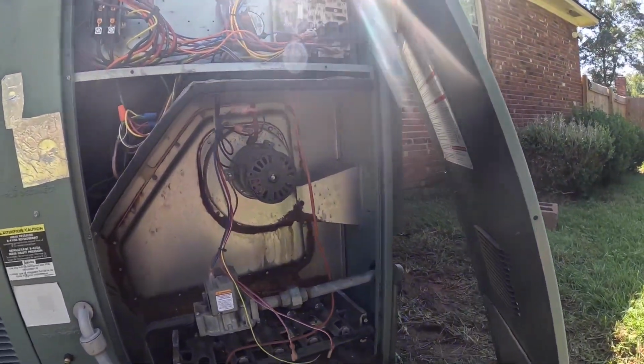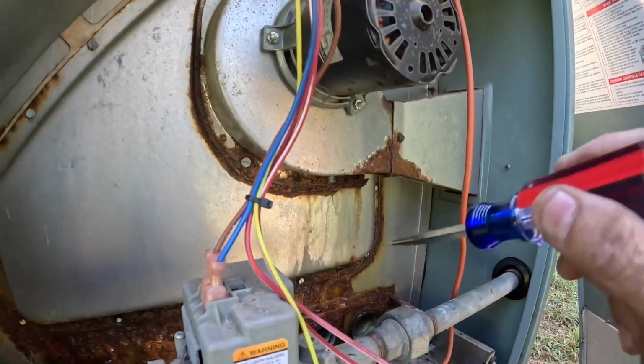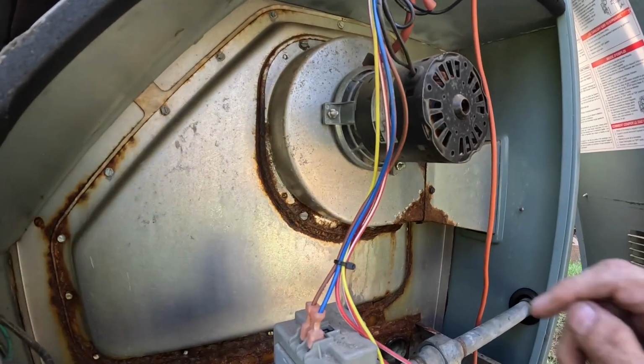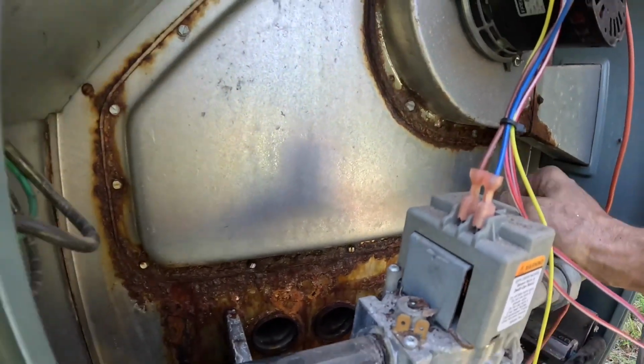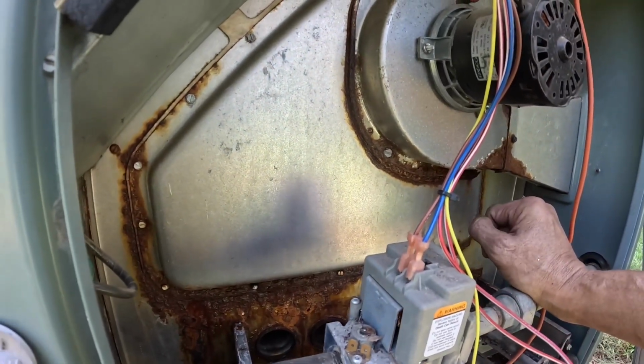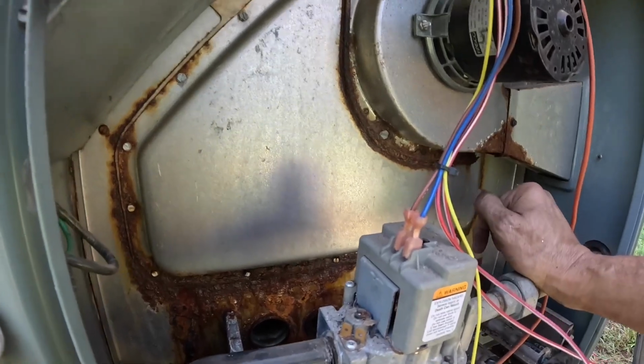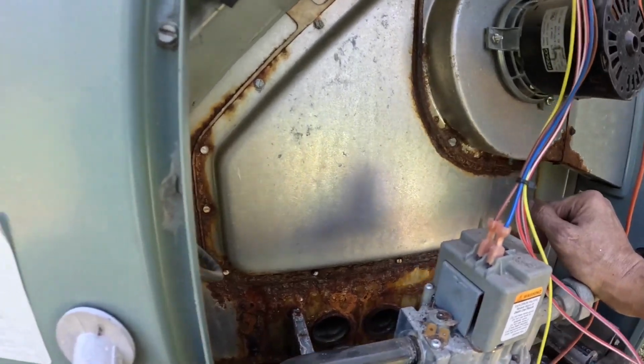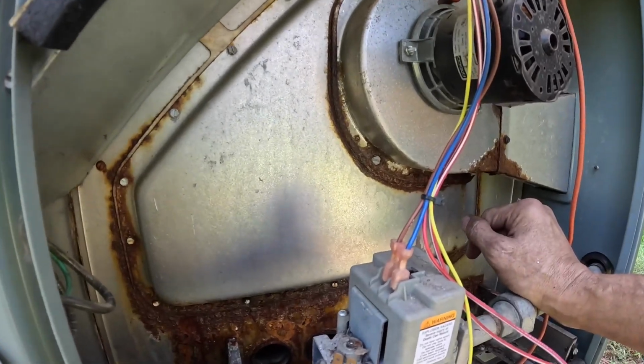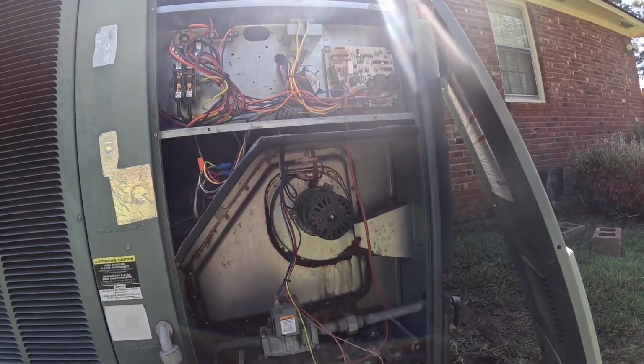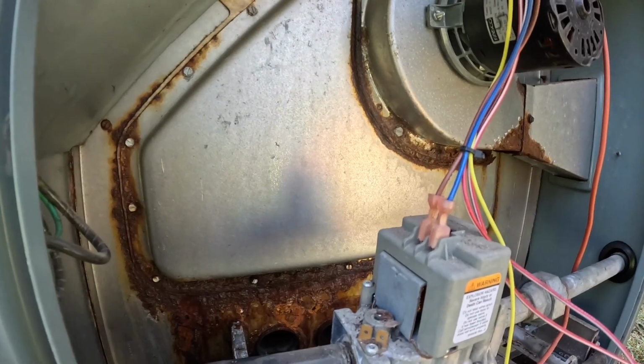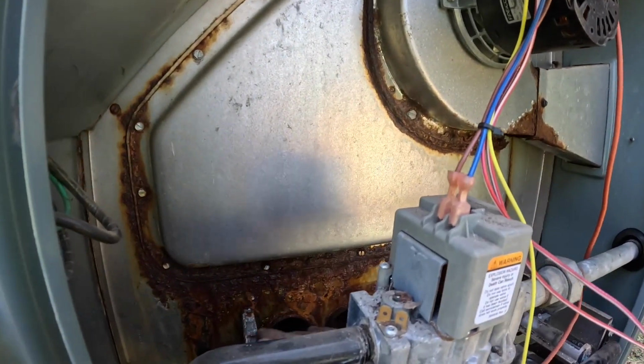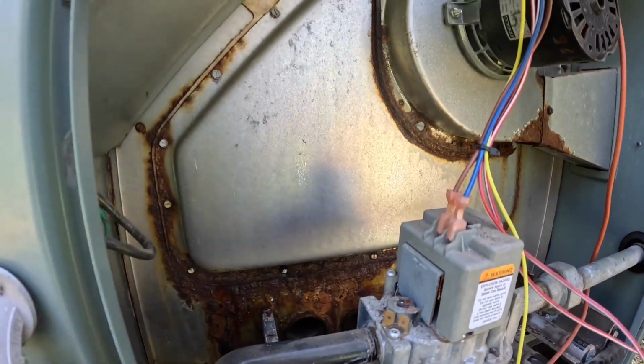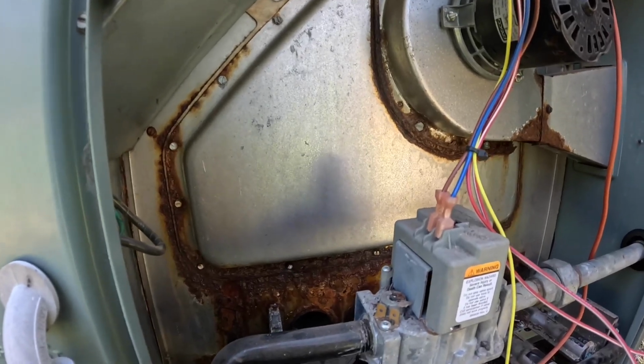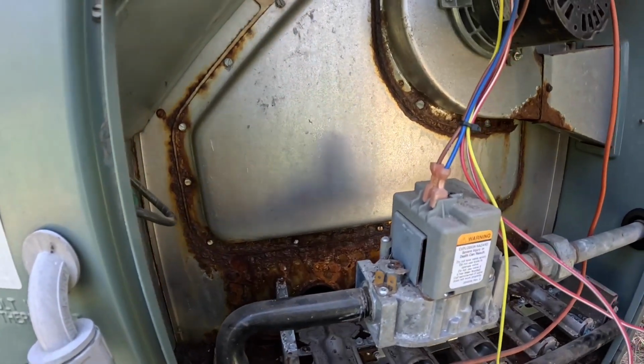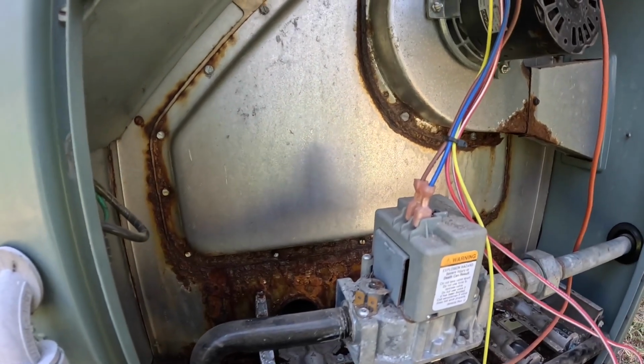I've talked about this before, but these rust like this so bad. And here's the reason. These tubes down here, the heat exchanger, when it's running in cooling, they're full of hot air. So that cold air is blowing over these tubes and water condenses in them. And if the water don't run out in here and in here, it's going to build up in the heat exchanger, and the first time you try to fire it up, there's going to be water in your heat exchanger.